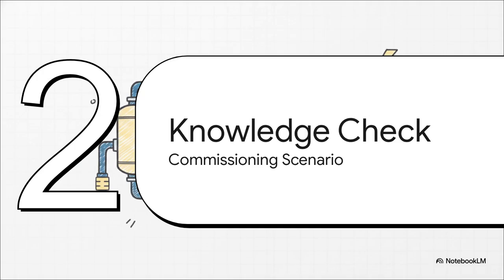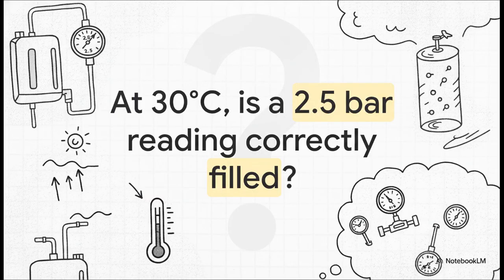Section 4, Knowledge Check. The commissioning scenario. All right, let's put this into practice. Imagine you're an engineer standing in a sweltering switchboard room. Let's see if you can apply these rules on the fly. Here's your scenario. You're commissioning an HPA breaker. The ambient temperature in the room is 30 degrees Celsius, and the pressure gauge reads 2.5 bar. Think back to our numbers. Is this breaker correctly filled, or is it underfilled? Take a second and lock in your answer.